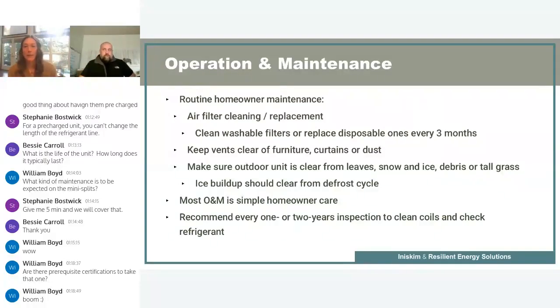The recommendation is every 1 to 2 years to have the units inspected. As I mentioned, my parents went 20 years and finally got their coils cleaned. Inside the head unit there are coils that can get debris buildup or, in some cases, mold buildup. Newer units tend to have a dry mode that helps prevent mold formation in the home, so if they're run in that mode, hopefully buildup is minimized. But it's still good to get the coils inspected. If you can get up on a ladder, you can look at the coils and see if they're getting buildup. There are kits you can order online to clean it yourself, or you can bring someone in, that's another great workforce opportunity. If you've got housing folks or local contractors who know how to clean those coils, getting them cleaned regularly helps the unit operate more efficiently.